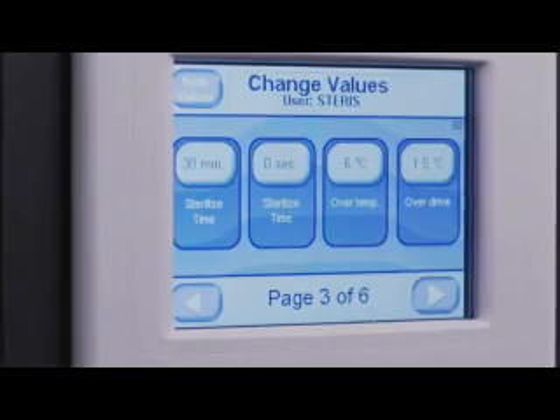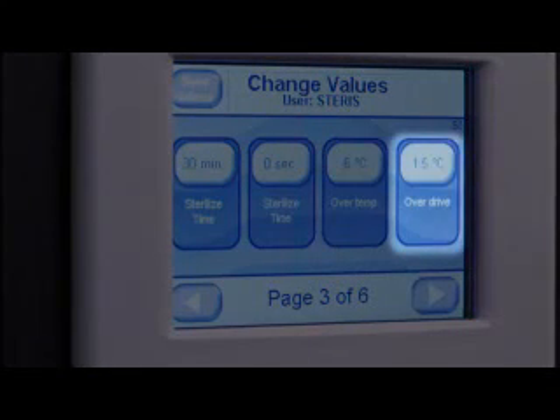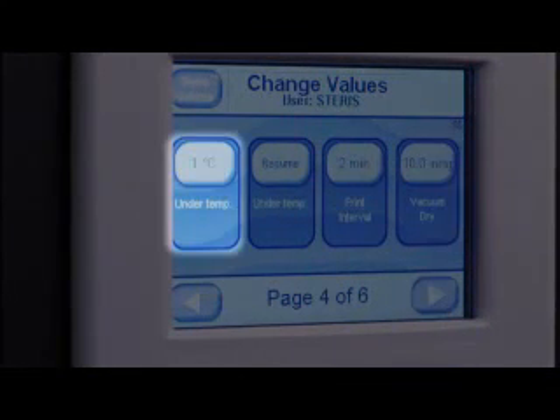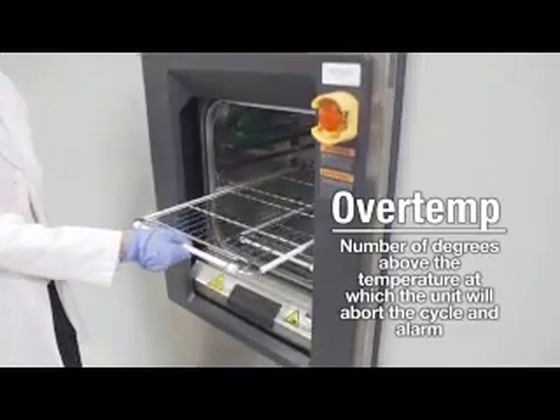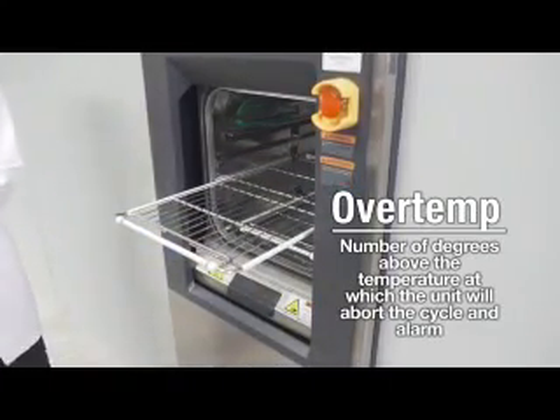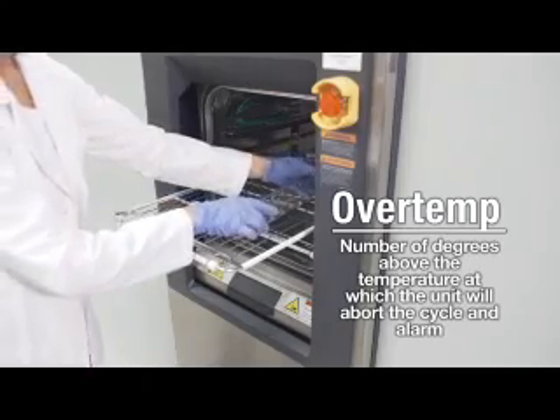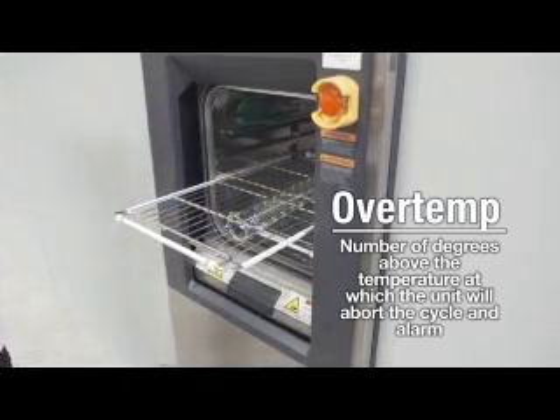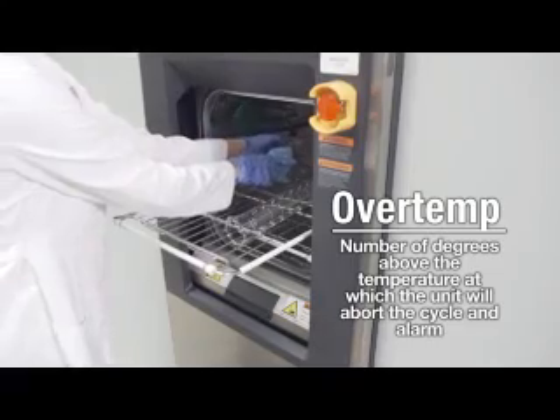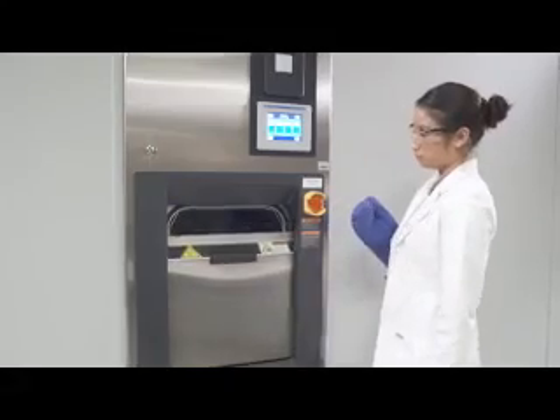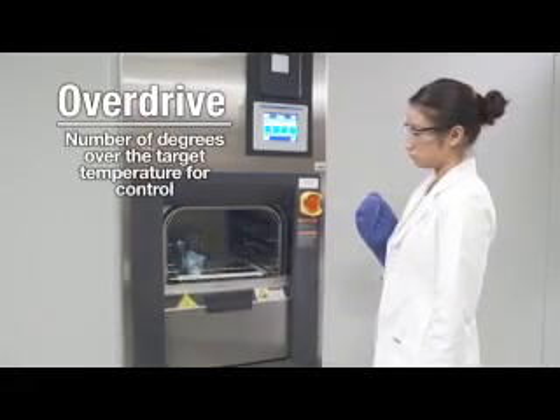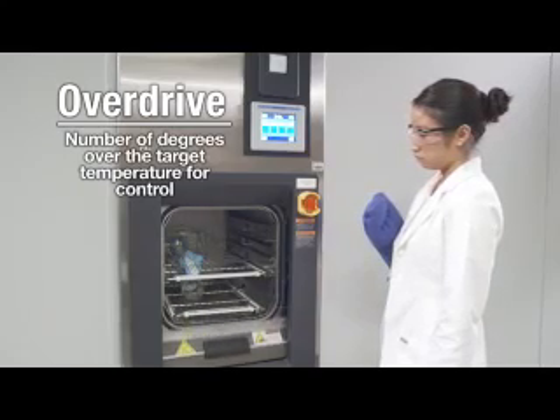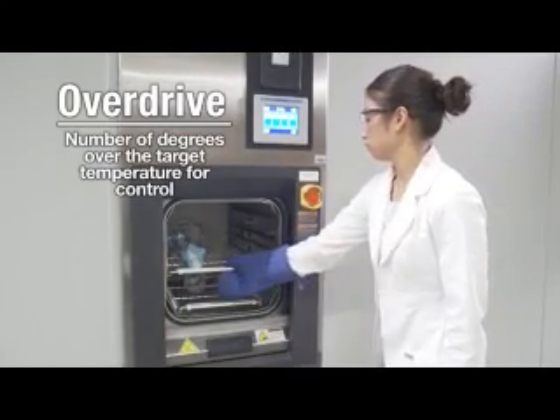There are a few other cycle parameters to be aware of, but for a rare exception, should not need to be modified. These selections are the over temp setting, over drive setting, and under temp setting. The over temp button is set at the factory and should not need to be altered. This is the temperature at which the sterilizer will abort the cycle. This is a safety setting that prevents the sterilizer from heating the chamber to an excessive temperature. The overdrive is a target temperature in excess of the preset sterilization temperature. It ensures that the needed sterilization temperature is reached.